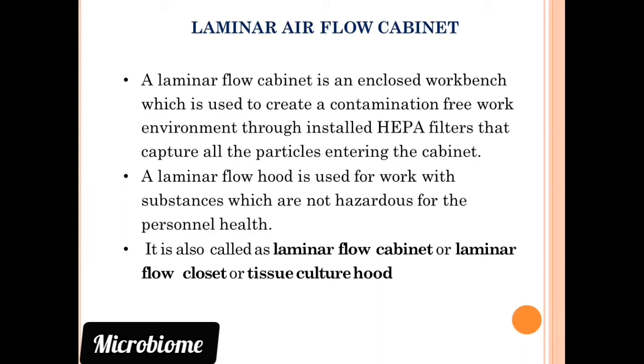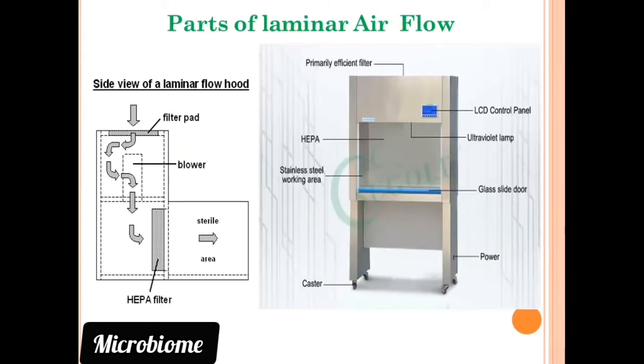So basically, laminar airflow cabinet is used where we need a contamination-free work environment. Mostly it is used in pharmaceutical units and is also preferred for research work. Now here are various parts of the laminar airflow. You can see there is a primary efficiency filter, also called a pre-filter, through which the air present in the room first passes.